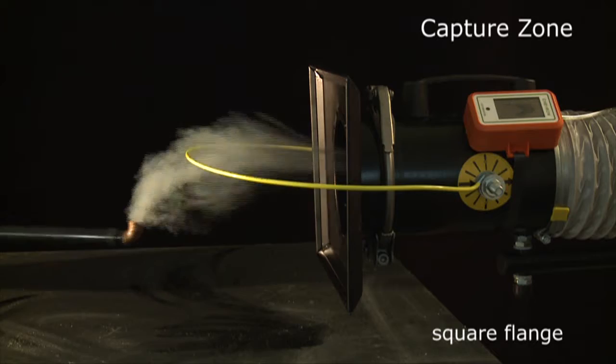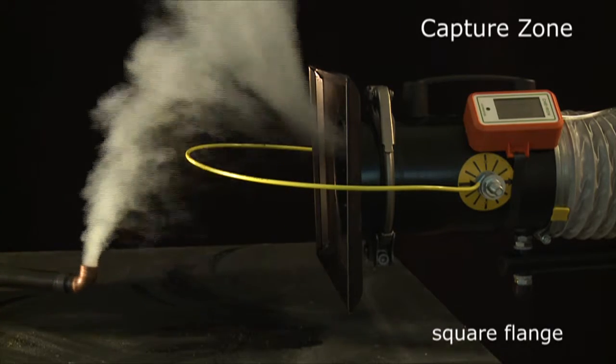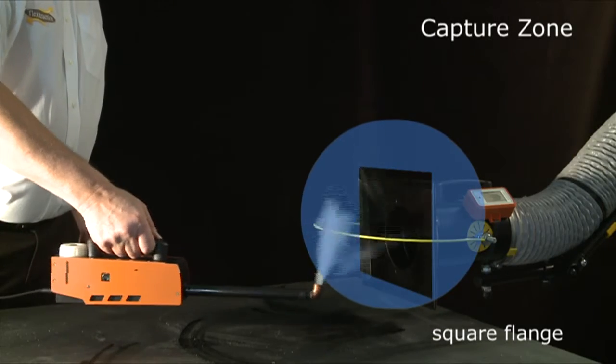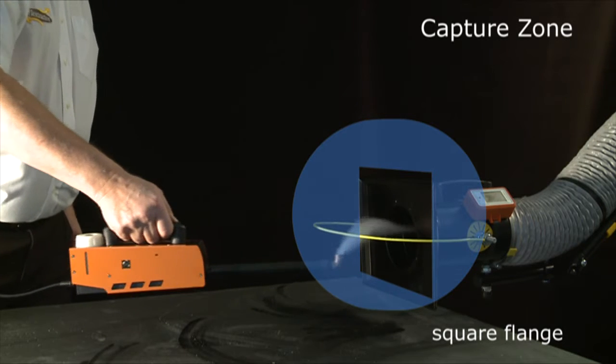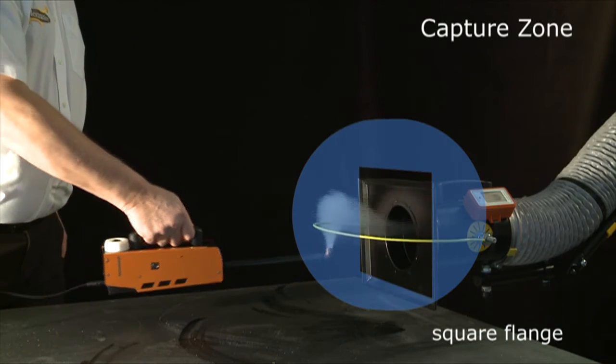A flange restricts the movement of air from behind a hood, changing the shape and extending the capture zone in front of the hood. It reduces turbulence in the airflow into the hood, which improves the effectiveness.